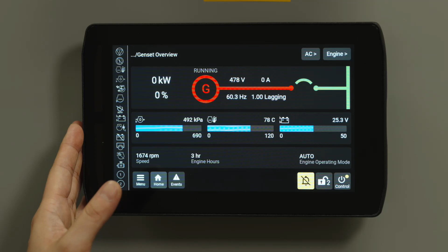Due to the loss of utility, you'll see a warning event, which I can acknowledge by pressing the acknowledge button. Once the genset has sensed the utility has returned and is stable, or the gen-to-utility transfer delay bypass timer has expired, the power will transfer from the genset power back to the utility power.